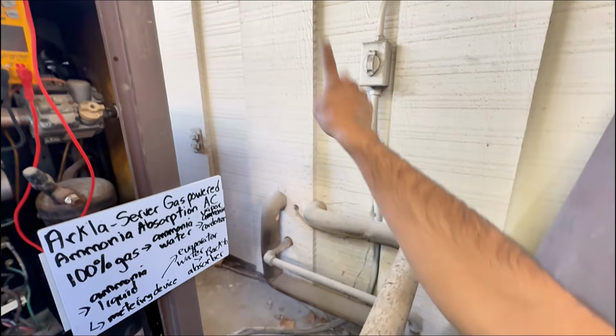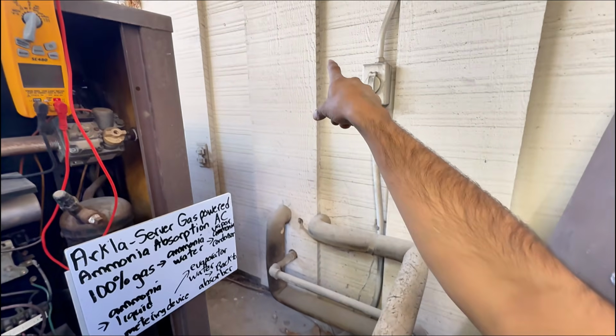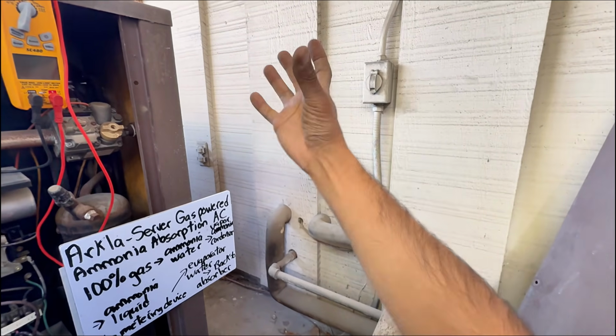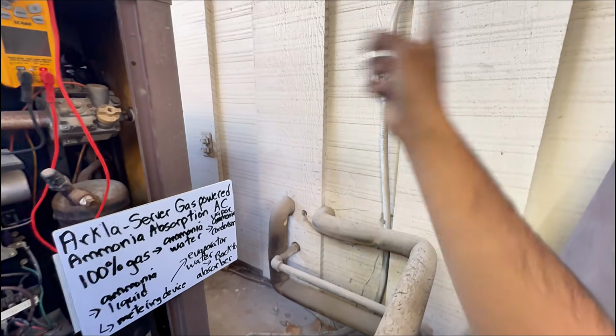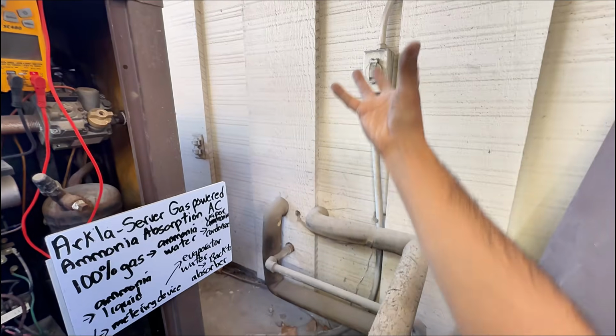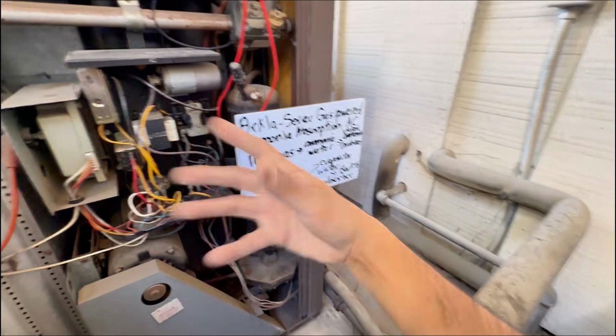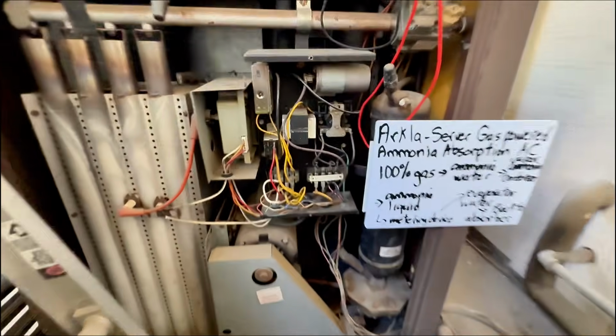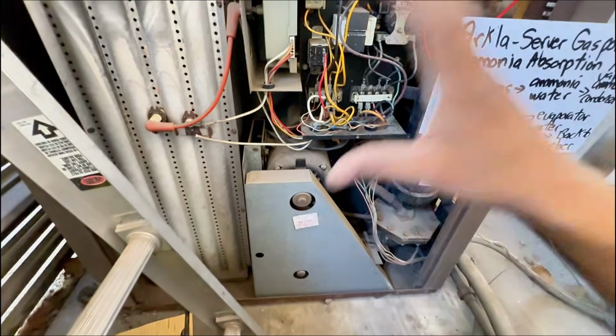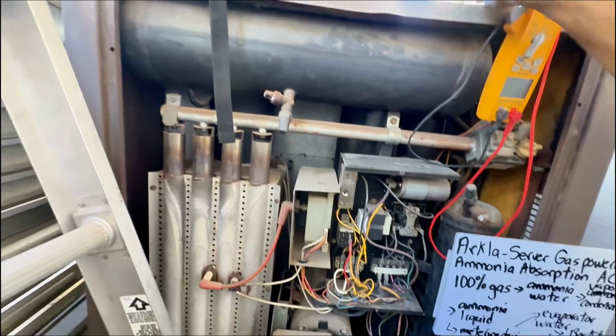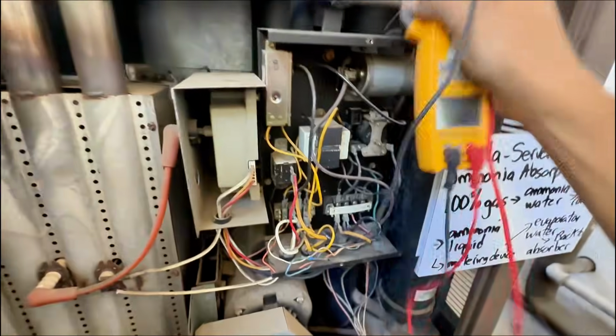But now that warm water, because it went through that cold evaporator, is coming back cold, and that cold water then goes inside to an indoor coil, and you're inside of the house, and then you have the return air going through that cold coil full of water, cold water, not a refrigerant, just cold water. That cold water picks up that heat, and then it comes back at 50 or 60 degrees, and it does the same cycle over and over again. That's all it is with this system, at least. But you know what? The gas turned off. I guess I can see if we have 24 volts going to the... So this pump right here, we can troubleshoot it together. I honestly don't know what I'm doing right here. So let's see. But I have an idea as to what to check.